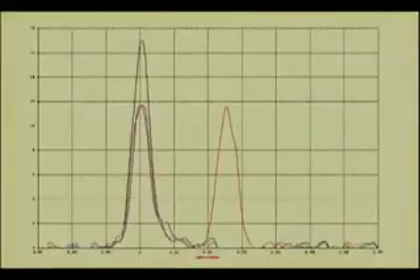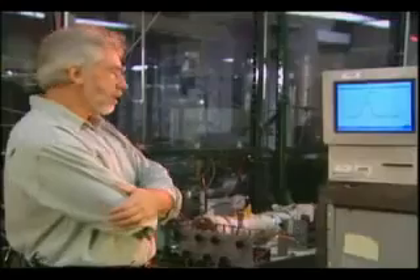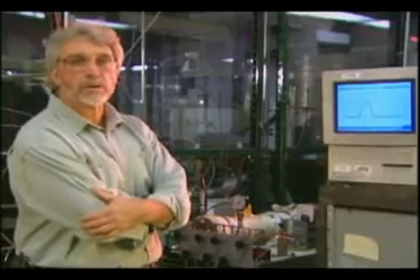On the monitor, you see displayed the mass spectrum from one of these samples. This is a relatively high level of helium-4. We compare the samples each day that we perform the analysis. We compare the sample of gas from the various active cells and blanks with a sample of room air, which we have measured many, many times and know to be 5.22 parts per million.